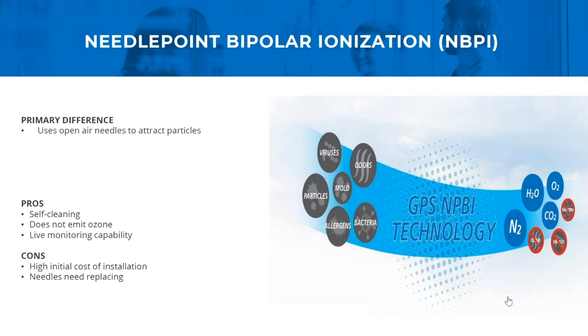Some of the pros to needlepoint is that they're self-cleaning. It's got a set of rotating brush heads that clean the needles and keep it working efficiently. Most of them, I should say, are UL listed as zero ozone emitting devices, and they have the capability of monitoring live and real-time streams within your BAS. The cons to needlepoint bipolar ionization that we have seen are the initial high cost of installation, and then over time, those needles that I mentioned earlier eventually have to be replaced. So those would be a couple of the pros and cons that we have.